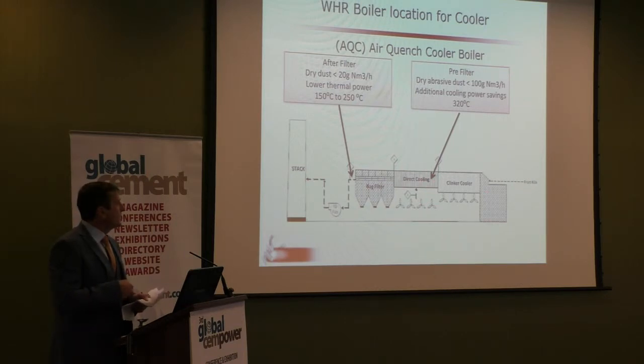Placing the heat exchanger to do the work of the cooling fan, or take away the induced draft that's going in to cool it, can save a lot of power from the fans or from the ID fans. And typically, we're finding there's an extra 10% of electrical efficiency or savings from the cooling fans, and maybe up to 30% when you are pushing in forced air. It's going through your bags and through your fans. So there's lots of additional savings from the fan side of it that can improve the payback and return on investment for the projects on the cooler side.